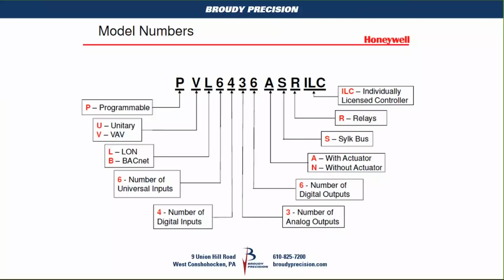The unitary flavor of the Spyders has a relay type, which has hard 4 amp at 24 volts AC, real relays built in, and a number of commons available to those relays for multiple transformer applications. If you had a cooling transformer and a heating transformer, and maybe a third or a fan transformer, you could separate all those powers with the relay type Spyder. Whereas the standard Spyder, the one without the R, you do not have that option, and isolation relays would be required.